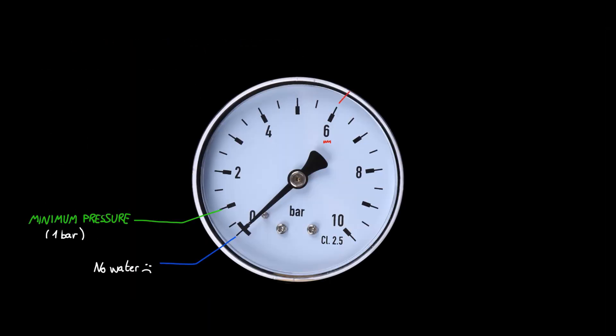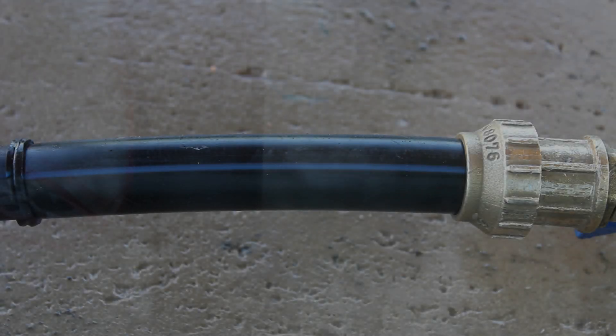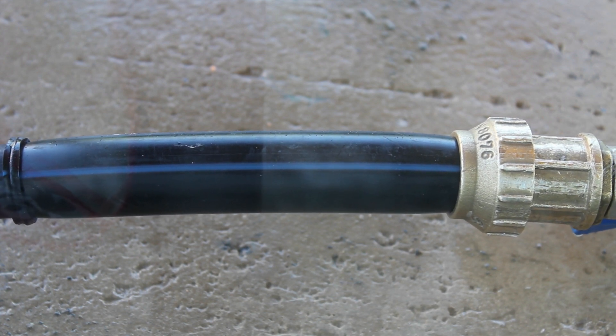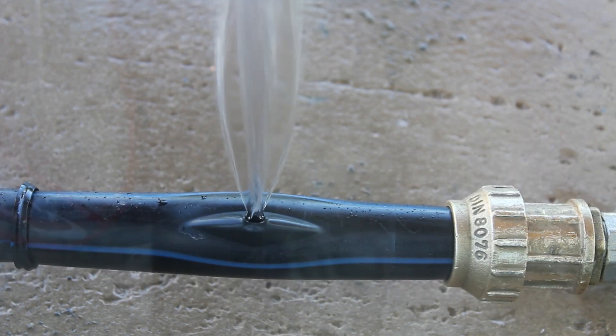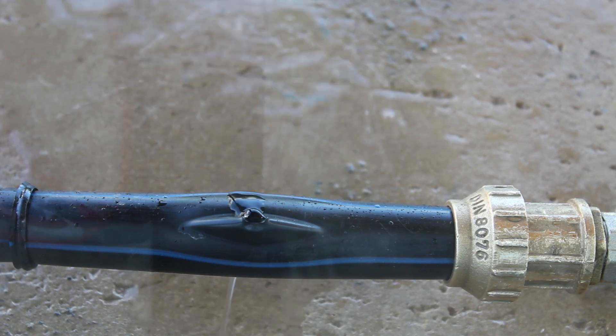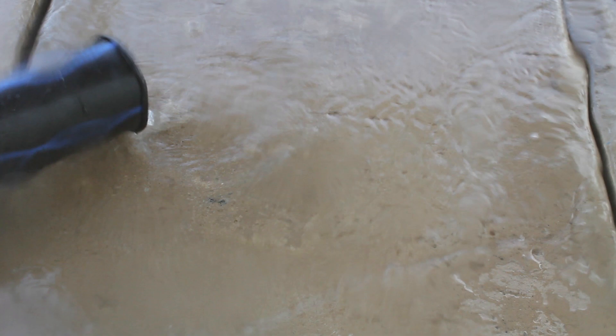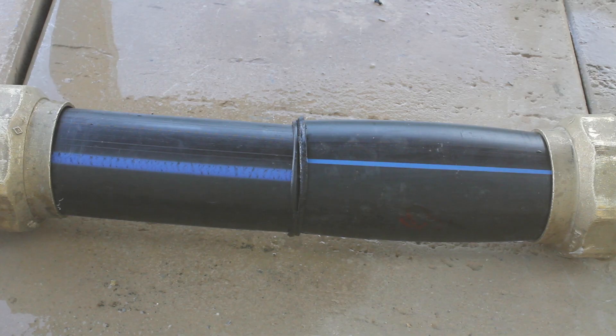The maximum pressure is set at 60 meters. There are a few exceptions to these 60 meters that we'll come back to in a minute. Having a very high pressure may seem great to reach all users. However, it's one of the main causes of leaks, damage to pipes, wasted water, and flooding. These events and their consequences grow greatly with pressure. Pipes are usually rated for 10 or 16 bar, and pressure has to be kept well below that to leave some margin for water hammer.